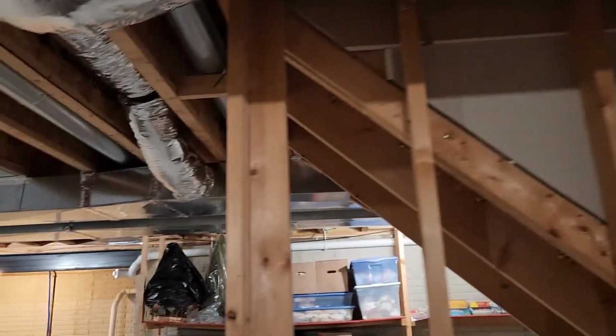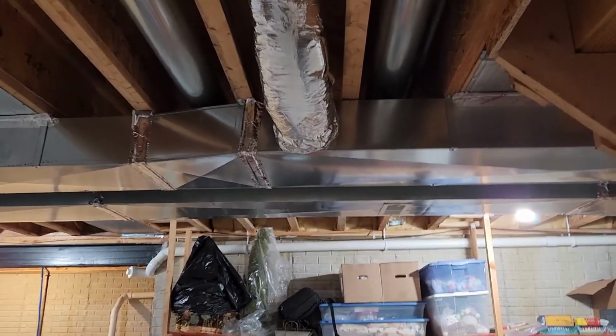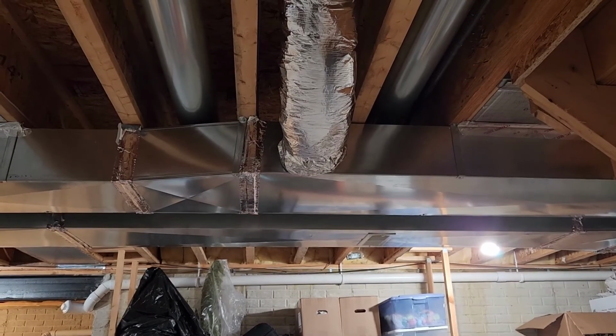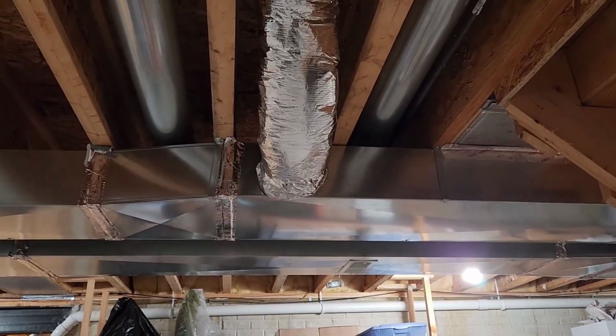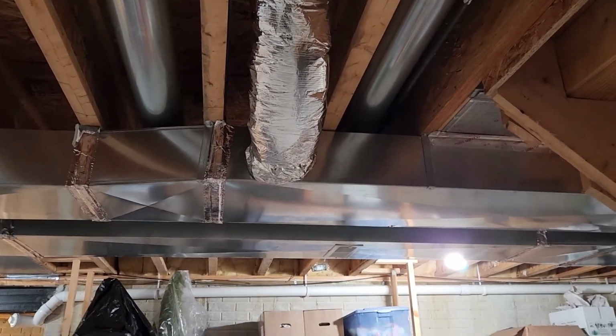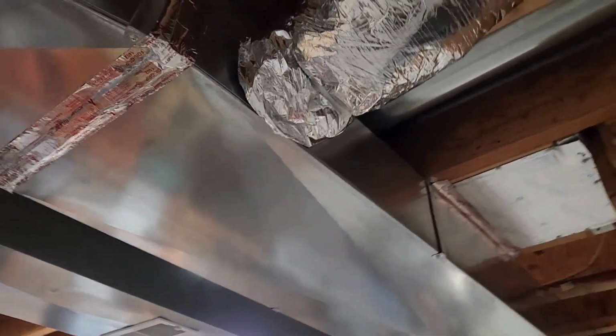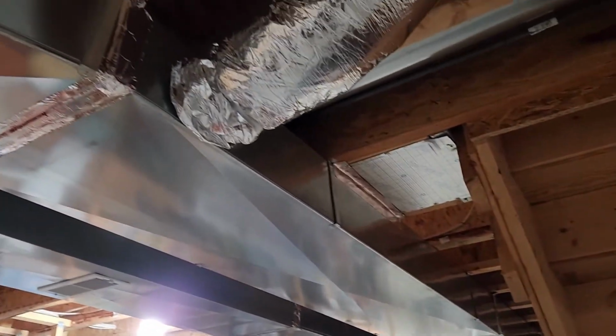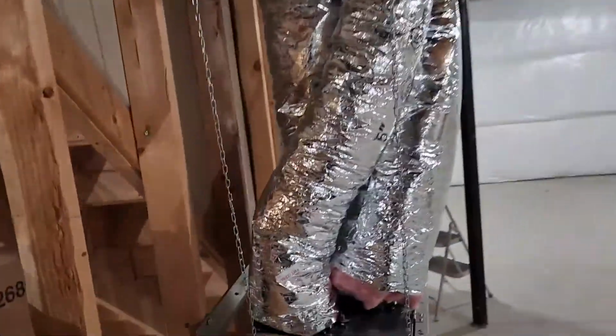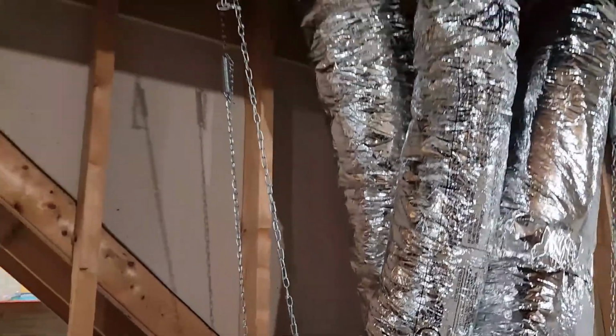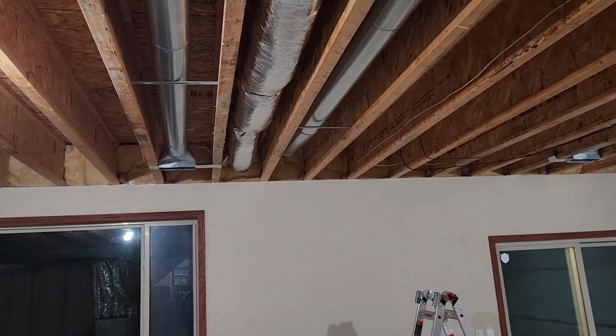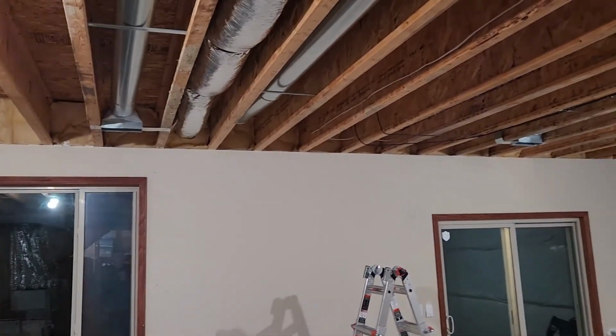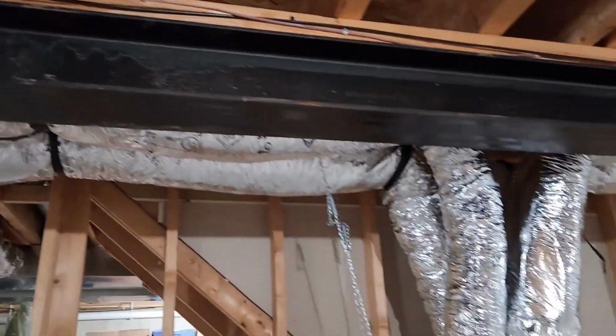As I was showing you guys earlier on the diagram, I'll show you the four individual runs. So here's the return air run where it comes in. I did buy the Klein duct cutting tool that you can hook up to your drill that makes really nice circular cuts. So I made two holes in my return duct. This is the return air one, which pulls in the return air, comes down and goes into the ERV, and then you've got the exhaust air vent that comes out and runs to my exhaust louver on the wall, and that's got a backdraft damper on it, which is nice. I'll show you guys the louvers. Those came from Fantech as well.